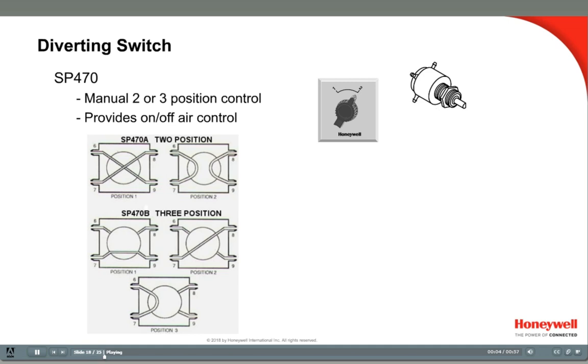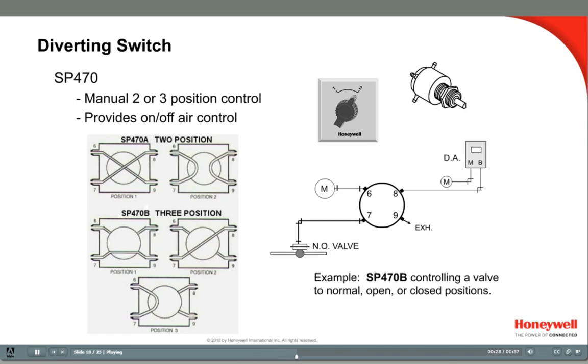The SP470 is a 2 or 3 position switch that can be used for on-off air control or diverting of pneumatic signals. With a 3-position switch in position 1, port 7 connects to port 9. In position 2, port 7 connects to port 8, with the other two ports blocked. In position 3, port 7 connects to port 6. In this example, a 3-position switch is connected to a normally open valve and a direct-acting thermostat. In position 1, port 7 connects to port 9 and the actuator exhausts so the normally open valve goes to full open. In position 2, port 7 connects to port 8 and the valve is under thermostat control. In position 3, port 7 connects to port 6 and main air is applied to the valve holding it closed.